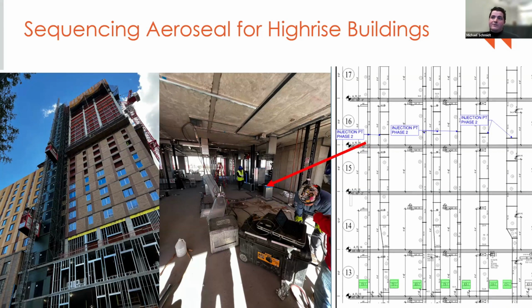They were sealing downwards from floor 16 after all of the ductwork, branch work, and accessories were installed on the lower floors. So they were able to cap off those areas, seal 16 downward, and then they came back and sealed from 16 upward. It's been very effective. We've been reviewing TAB reports, with buildings getting close to becoming occupied, and it's worked very, very well.